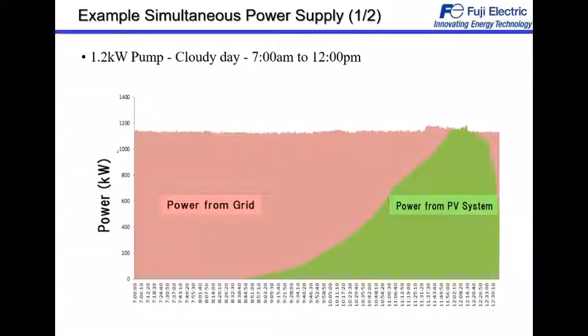This is an example of simultaneous supply where it's connected. We have a drive. It's a 1.2 kilowatt pump, so a 1.5 kilowatt drive. It's a cloudy day. Later we will see a bit. And this graph shows 7 a.m. to 12 p.m. So the drive is continuously checking if there is enough power coming from the PV panel. There is not enough at first. And we see around 8:38, 8:45 it starts taking energy from the panels and goes up to basically 100% around 12. Later it goes down, and this is exactly because it's a cloudy day. Otherwise, it would continue taking the power from the PV panel.